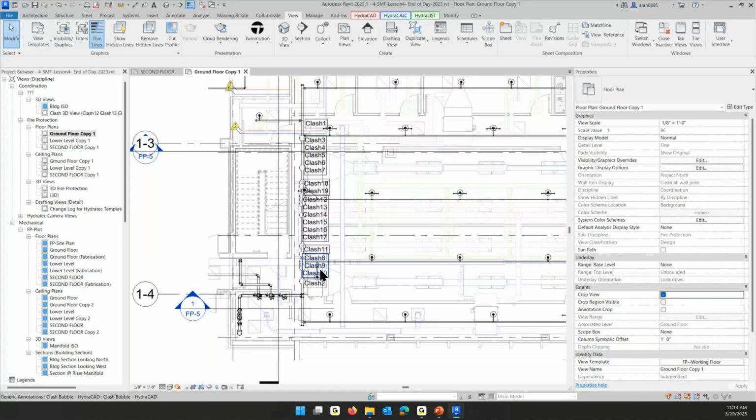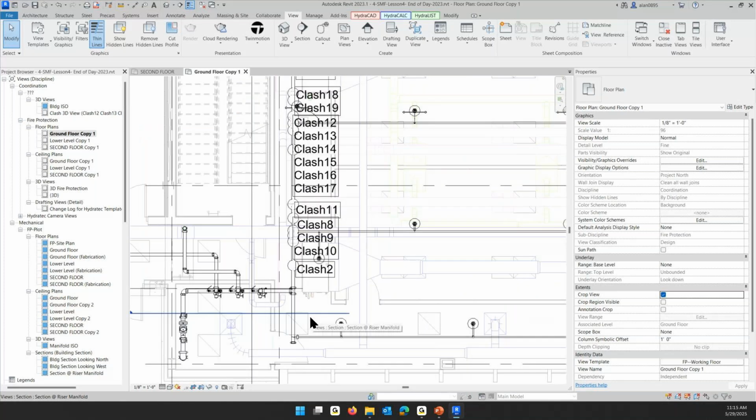So having looked at the big picture that says I'm hitting there, and most of those, it was like the main was too high. I'm going to propose simply moving the main down. I need to keep in mind, if I move a pipe, all the pipes parallel to it are going to move with me. Pipes perpendicular to me are going to get longer or shorter.